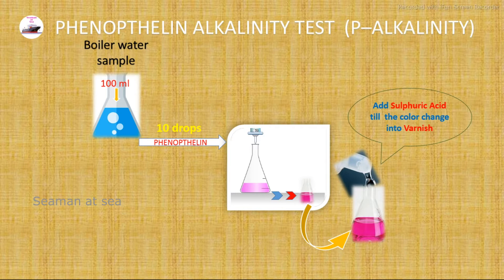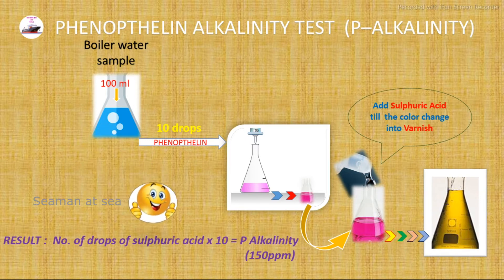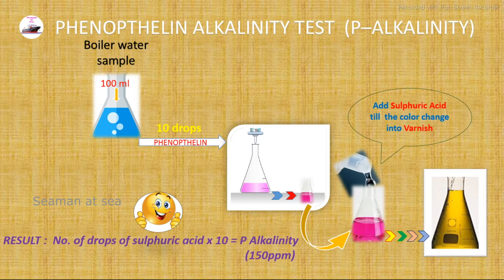The quantity of sulfuric acid added indicates the phenolphthalein alkalinity in the boiler water. The number of drops of sulfuric acid multiplied by 10 gives us the phenolphthalein alkalinity — 150 ppm is the acceptable value by every surveyor. This test is conducted to find out the hydroxide level in the boiler water.